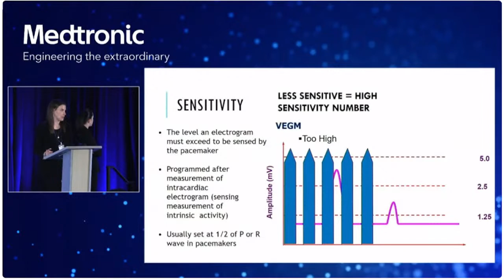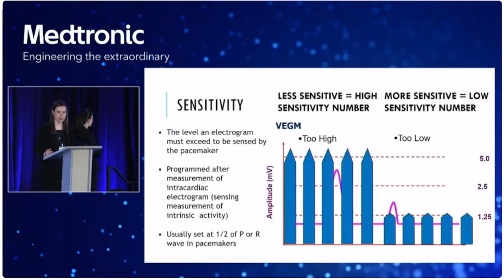Now, if a device has a high sensitivity number, that means that it's less sensitive. And sometimes you can set your sensitivity too high, so it can't see anything. The fence is too high. Now, you can also make a device more sensitive, which is a lower sensitivity number. You make it too low, then it might see too much. So it's important to set it right. So we want to have adequate sensitivity for a device, because once the signal exceeds the programmed sensitivity, it will be sensed by the device. So it's all about that fence, so that you have the level of the fence appropriate to the situation.